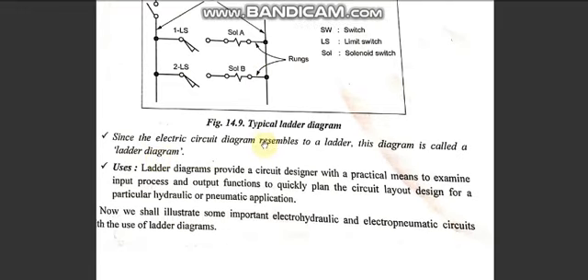A limit switch is shown — normally open. When the limit switch is actuated, it energizes solenoid valve A, which is connected to the direction control valve. The electrical components shown are limit switches and solenoid valves. When limit switch 2 is activated, solenoid B is energized. Limit switch 1 is connected to solenoid A and limit switch 2 to solenoid B, and when coupled, they get energized accordingly.